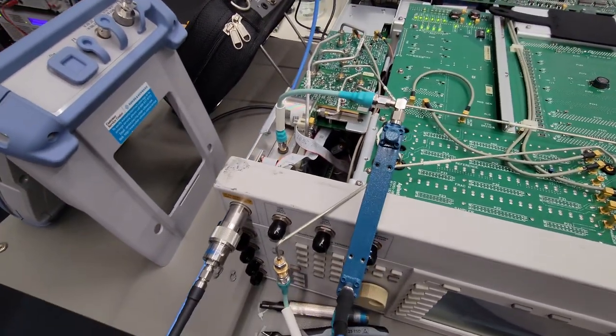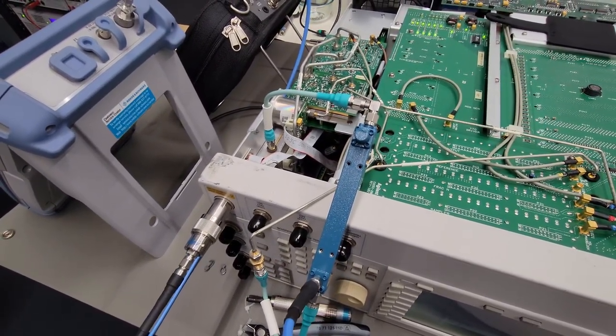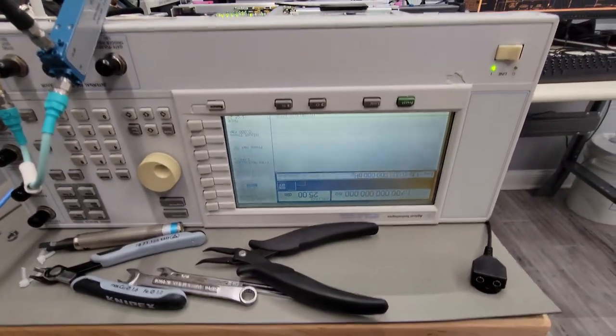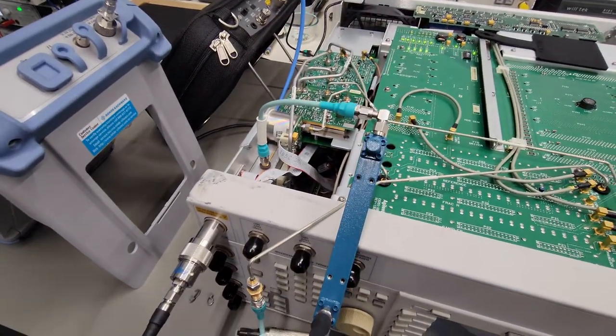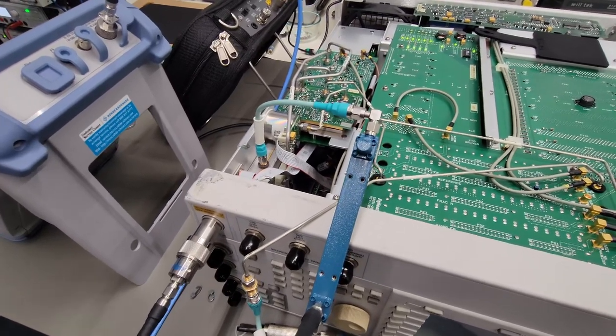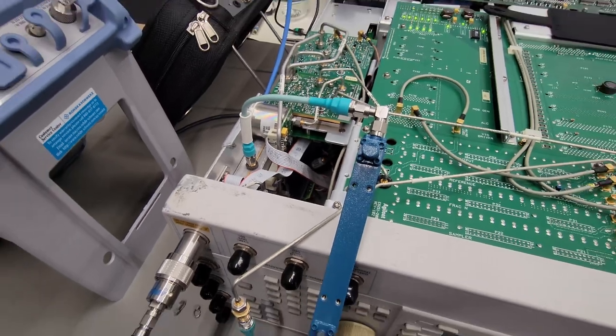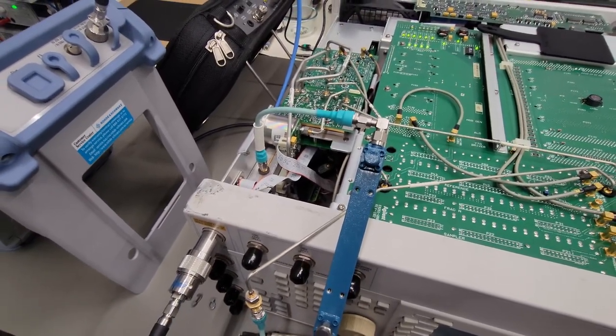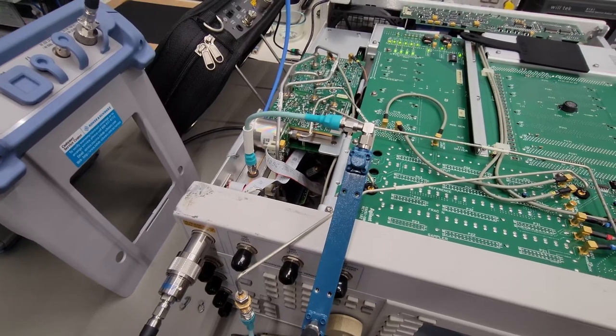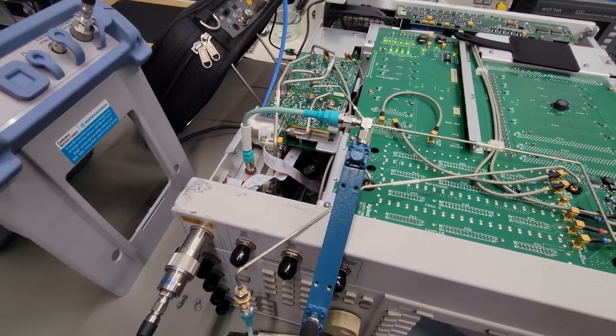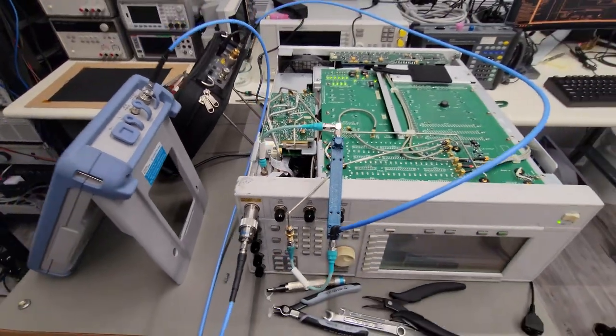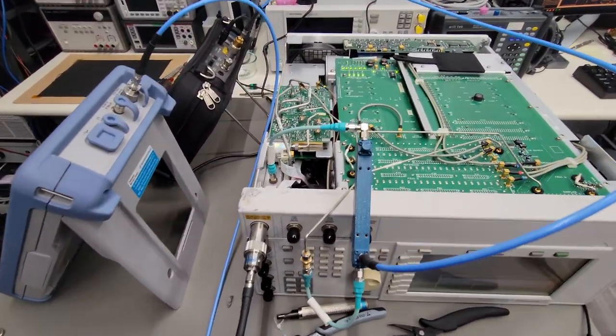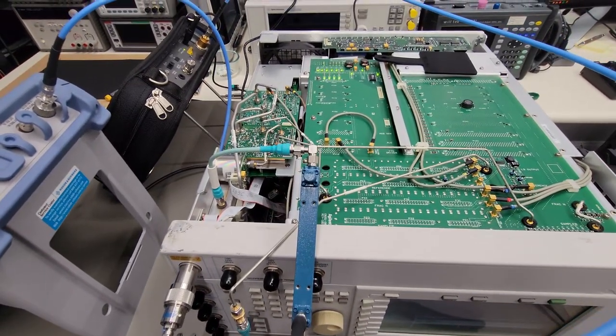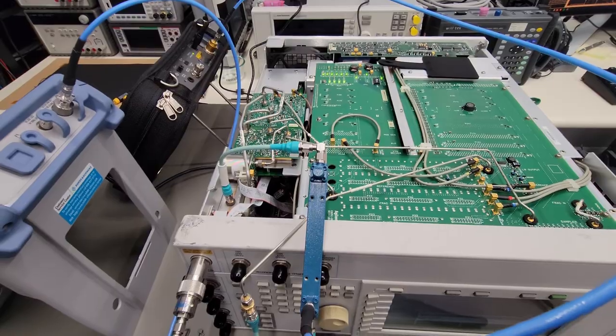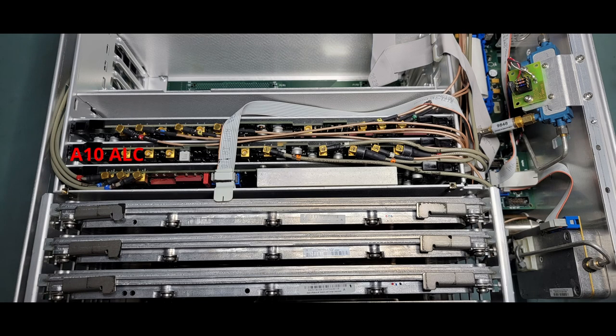So based on these symptoms we're seeing here and the fact that there are no on-level errors, this could very well be something going on on the A10 ALC board itself, probably an analog problem related to the DACs and the offset voltages that are used in the ALC comparison measurements. So what I'm going to do is flip the unit over after disconnecting and reassembling everything. Then we'll take a look at the A10 ALC board and try to understand how that works. The A10 ALC board is the second unshielded board that sits behind the YIG driver.